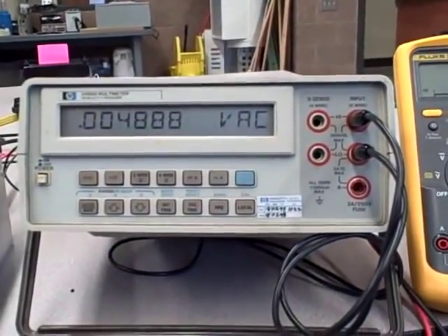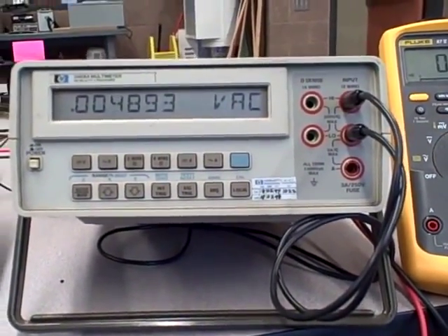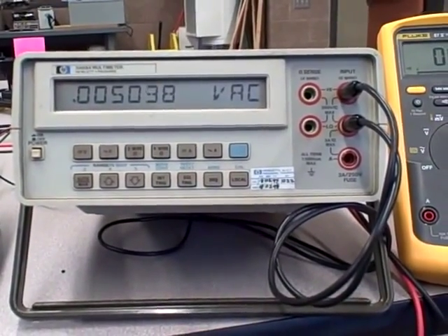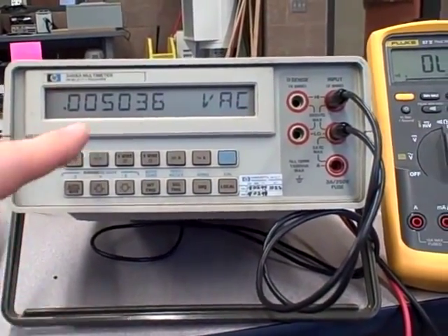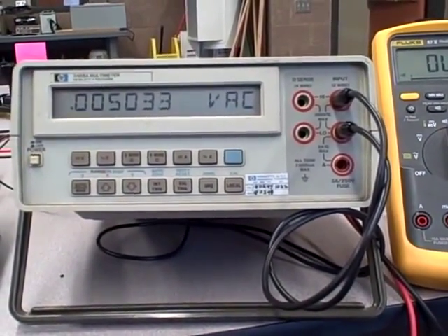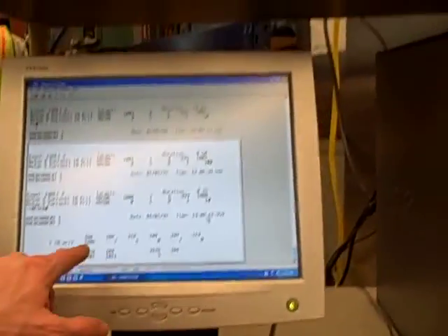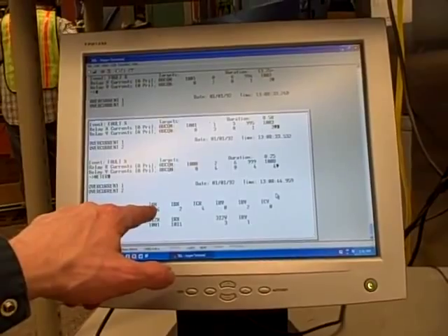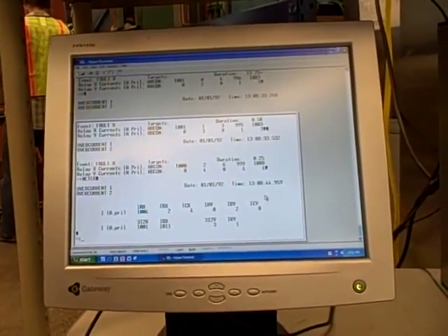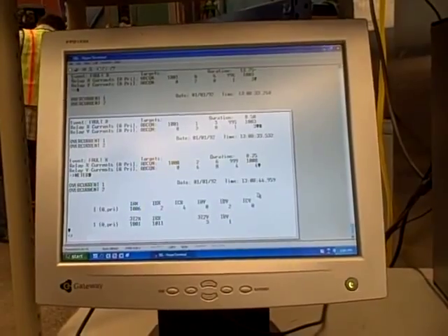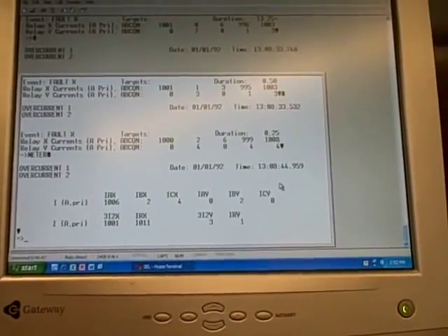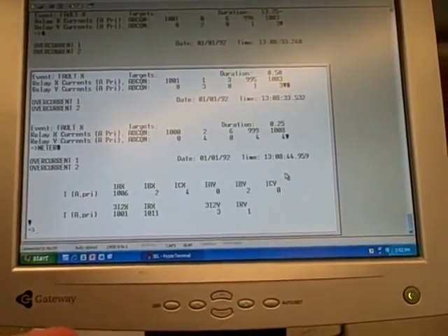I'm going to increase the current. I'm going to increase it until I see a current there at my HP multimeter of about 5 amps. Now remember, the relay is expecting a 1,000 to 5 current transformer ratio. So 5 amps here, 5 millivolts equals 5 amps, should be 1,000 amps in my power line. If I type in the meter command again, I see indeed 1,006 amps coming in on A phase for relay X. Now, my pickup value for time over current was set for 1,000 amps line current or 5 amps CT current. So right now, as we speak, that relay is very slowly timing.